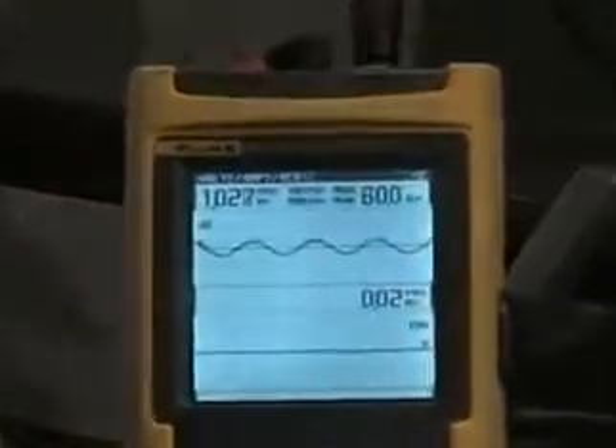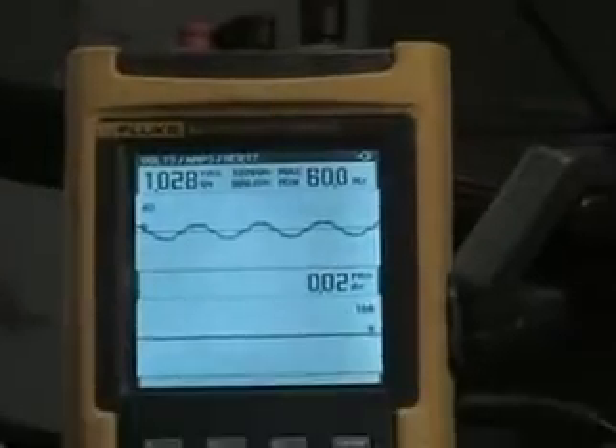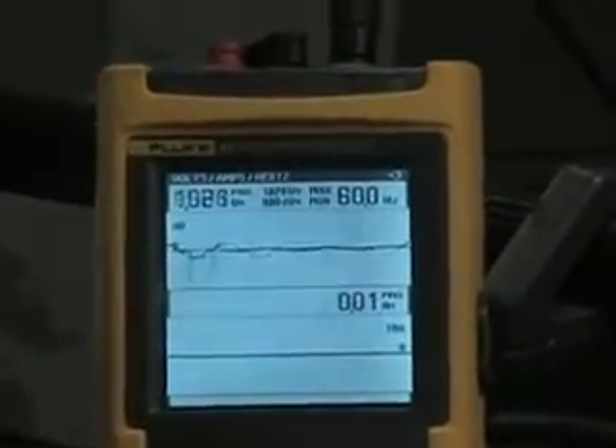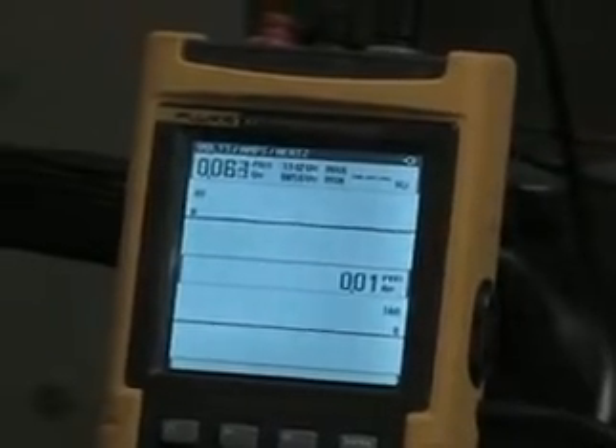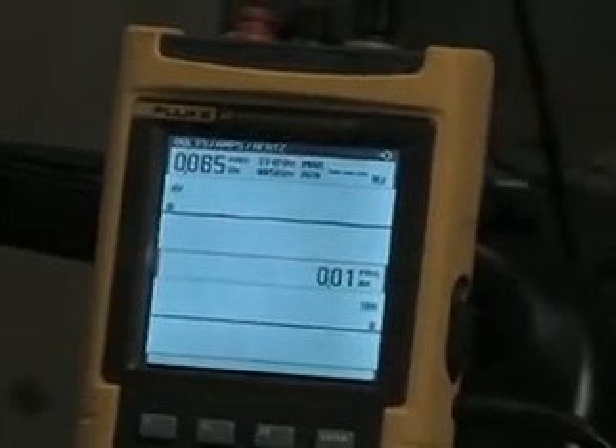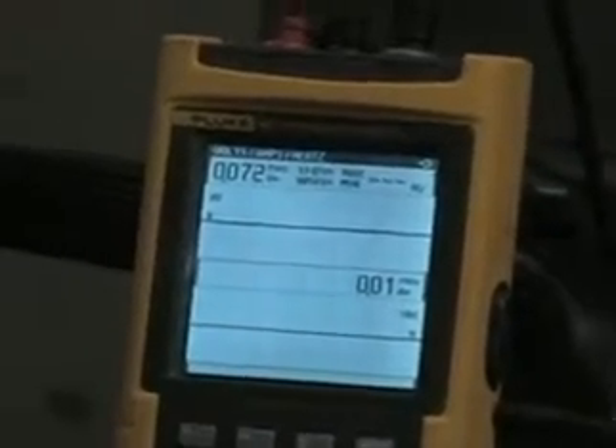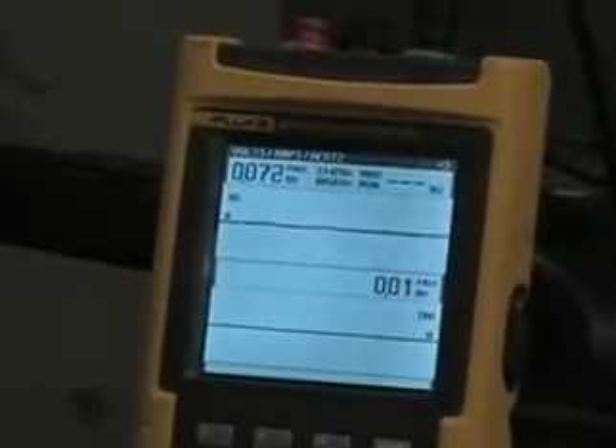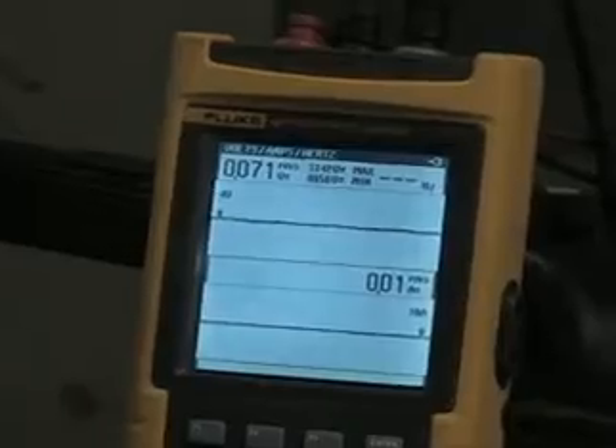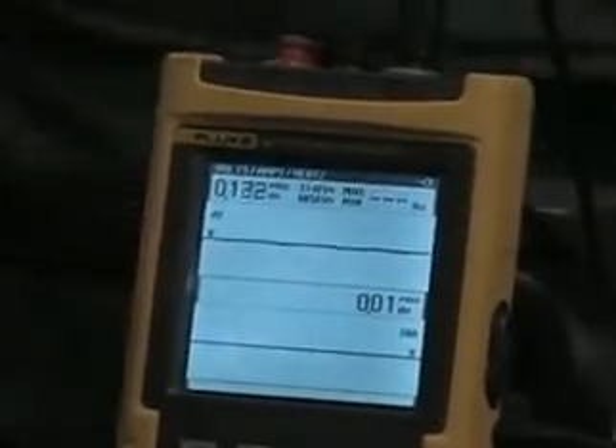We begin with the A phase. As you can see, there's a 1028 millivolt drop across the breaker. On the B phase of the breaker, it is significantly lower at 62 millivolts. And on the C phase of the breaker, it shows 71 millivolts. This test identifies a greater than 1 volt drop on the A phase contact. According to the NETA standards, this type of measurement cannot exceed a 50% deviation from one adjacent pole to the other. Our findings will now be presented to the manager of this facility.